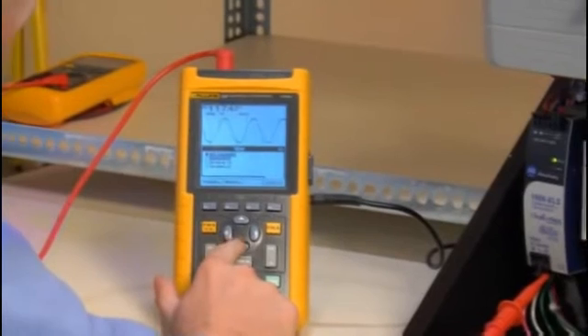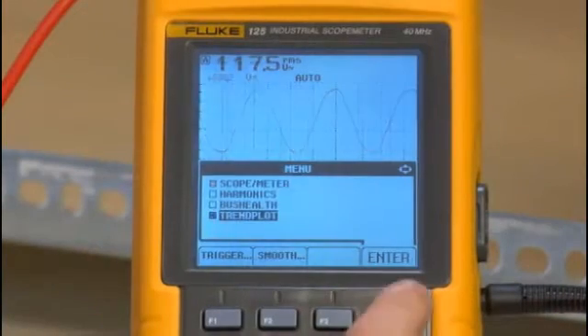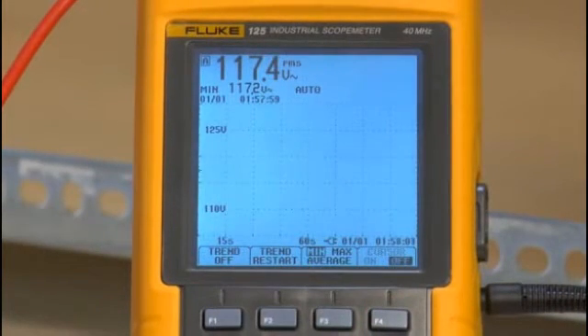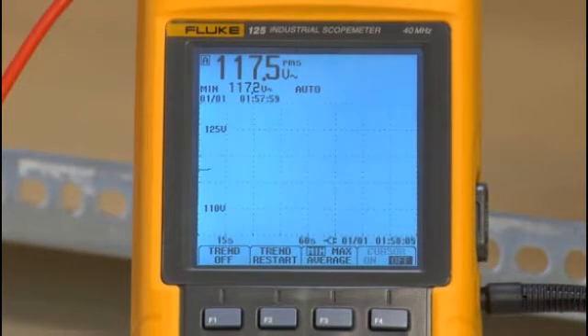If we don't see anything right away, we'll use the Scope Meter's trend plot mode to capture the input over time. Now we can go about our job while the oscilloscope does its job. If there's a disturbance, the Scope Meter will capture it and plot it just like a paper chart recorder, telling us the time and magnitude of the problem.